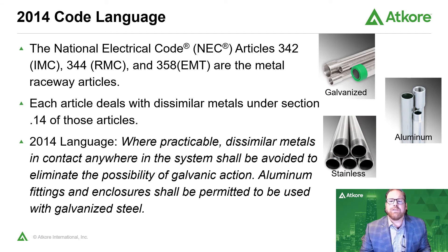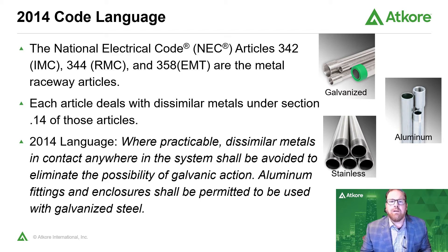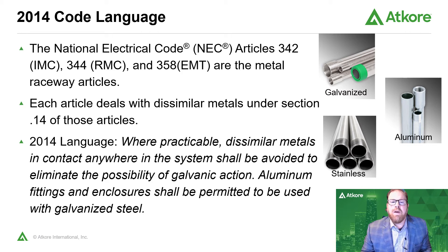In the National Electrical Code, Articles 342 for IMC or Intermediate Metal Conduit, 344 for rigid metal conduit or RMC, and 358 for Electrical Metallic Tubing or EMT are the metal raceway articles. These articles are all set up identically and have similar code language. Each article deals with dissimilar metals under section dot 14 of those articles. So for instance, 344.14 would be the dissimilar metal section for rigid metal conduit. The dissimilar metal sections all read the same in the 2014 code language, and then 2017 and 2020.